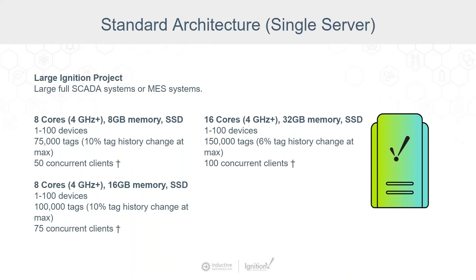For really large systems — full Ignition SCADA or MES systems, for example using the SEPASOFT MES modules — we're talking eight cores, 16 cores, and then numbers scale up from there to 75,000 tags, 100,000 tags, 150,000 tags, and up to about 100 concurrent clients.